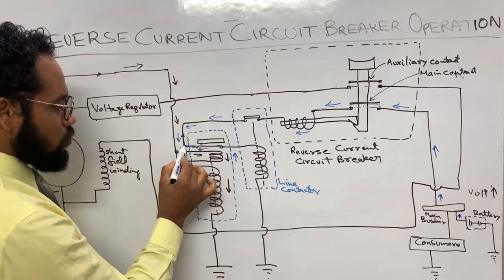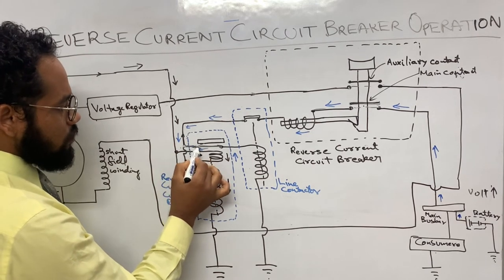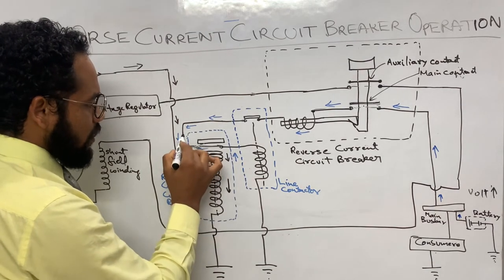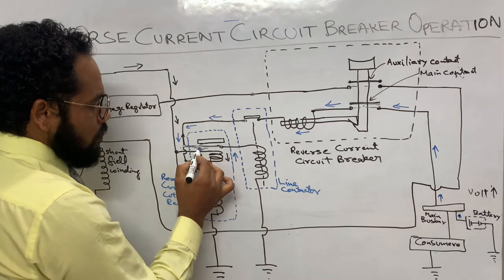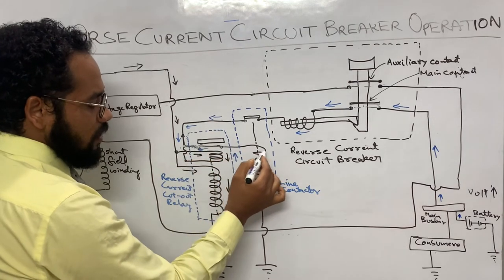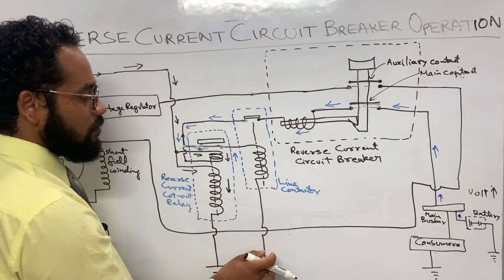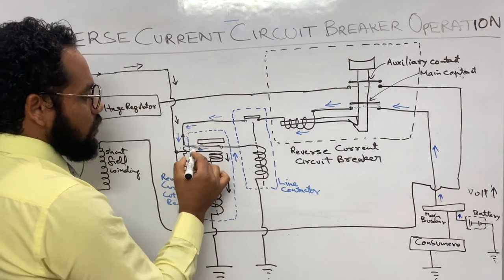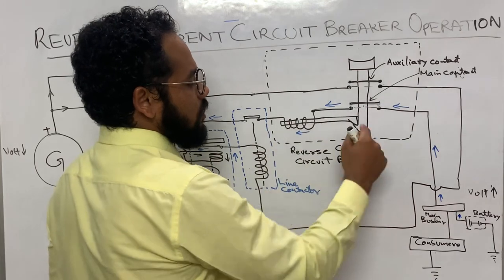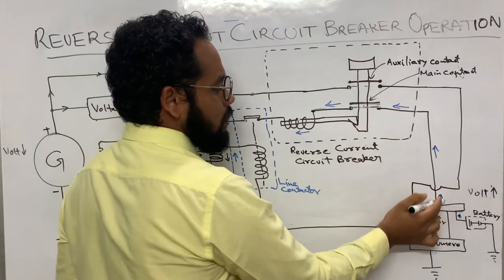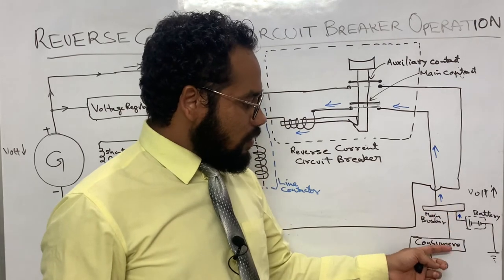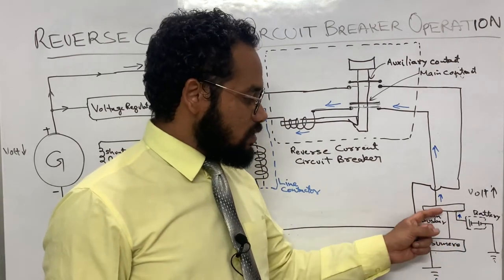The current goes in two paths — one through the voltage coil side and the other waiting at a point. Through the current coil path, the current energizes the coil of the line contactor, which closes its contact. Now the generator output current passes through the magnet system coil of the reverse current circuit breaker and through the main contact to the main bus bar and batteries. The consumer equipment and electrical loads on the main bus bar receive power.